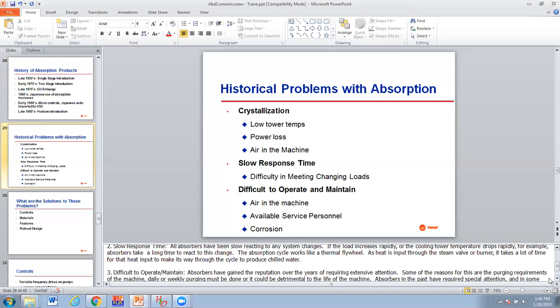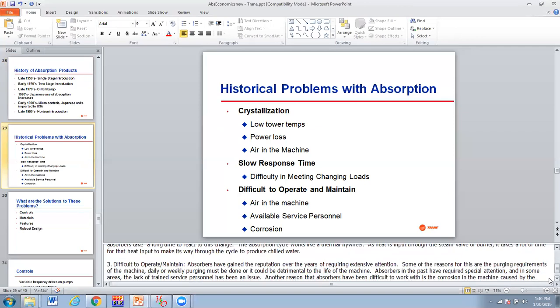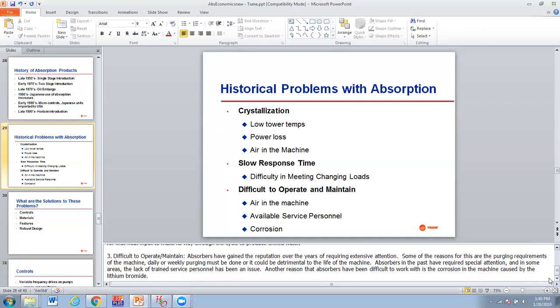As heat is input through the steam valve or burner, it takes a lot of time for the heat input to make its way through the cycle that produces chilled water. So changes in heat input take a while to be reflected in the output. And that's traditionally been the problem. Difficult to operate and maintain. Absorbers have gained a reputation for requiring extensive attention.